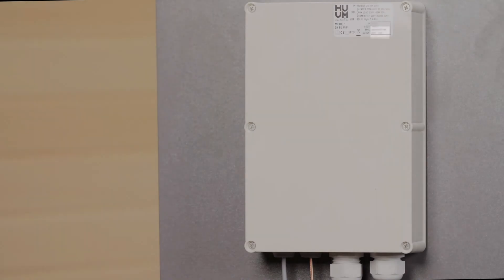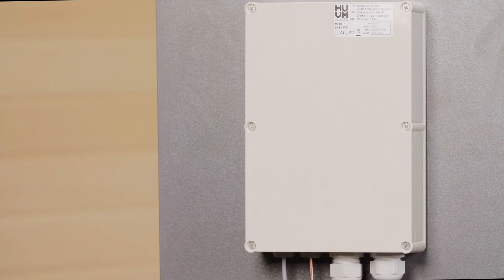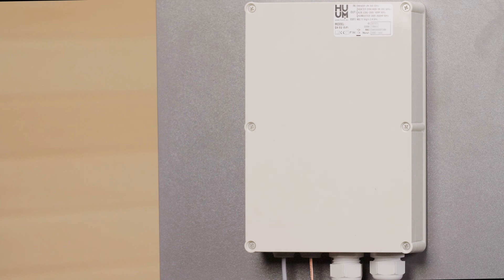Now let's find a good spot for the main module. It just needs to be somewhere that doesn't get hotter than 50 degrees Celsius and doesn't get more than 95% humidity. We've seen customers put this in all kinds of places, including in a technical room or under a suspended ceiling. We don't really recommend putting it inside the hot room if you can help it, but some people do if it's the only suitable space they've got available. If so, just make sure it's about 10 to 50 centimeters from the floor and as far away from the heater as possible. You could even place it outside, but then you should build some kind of protective cover for it.